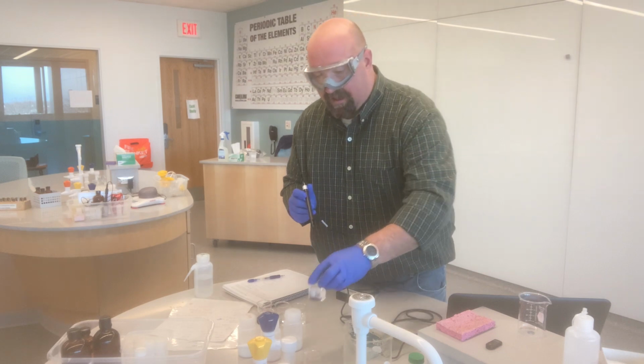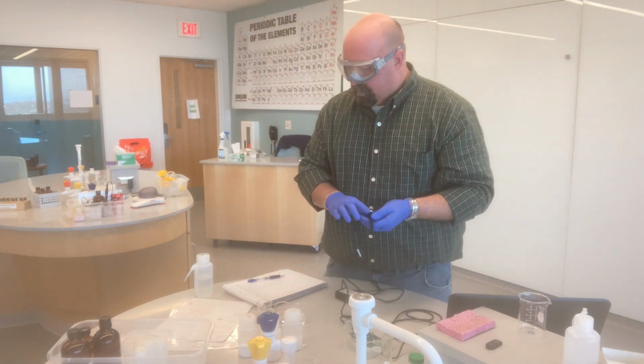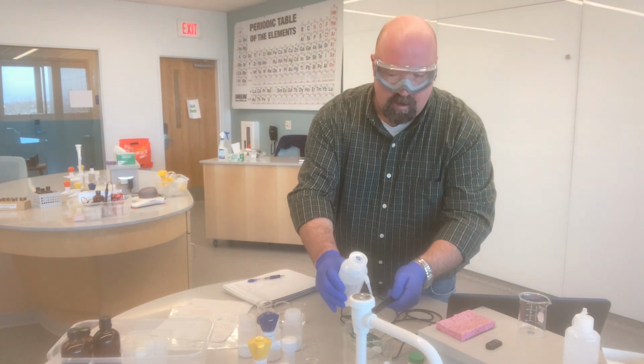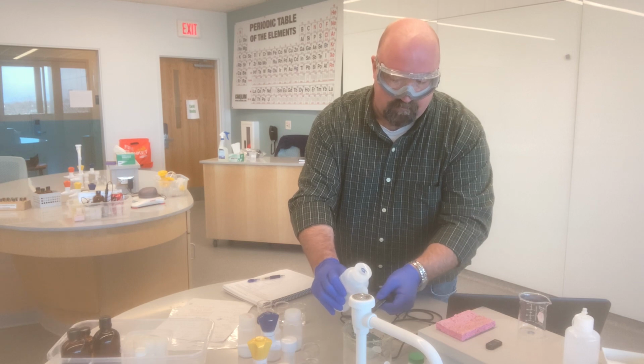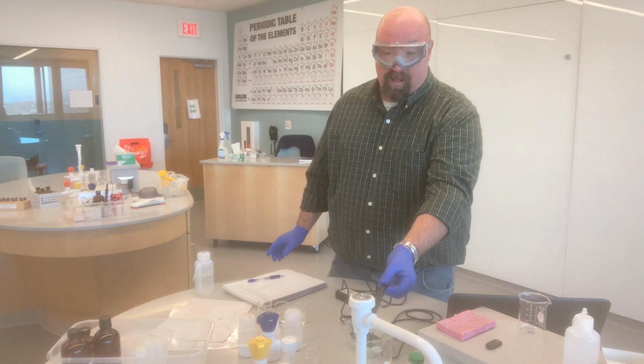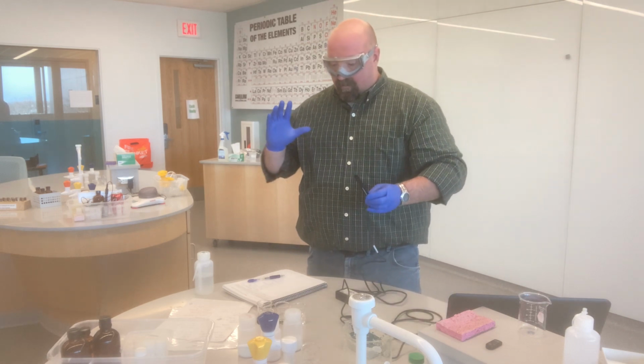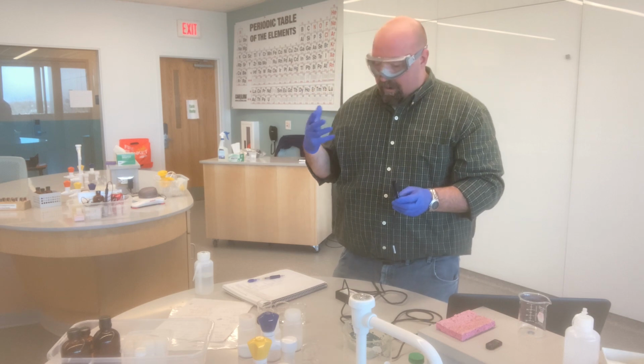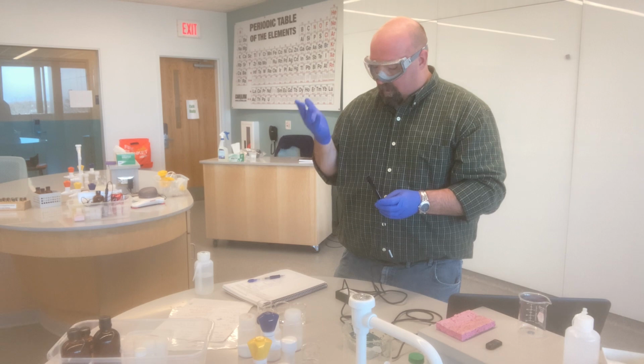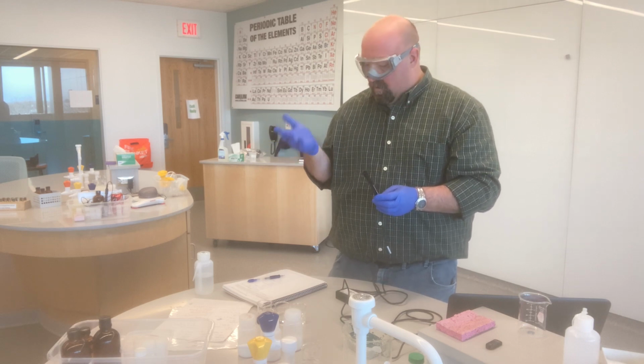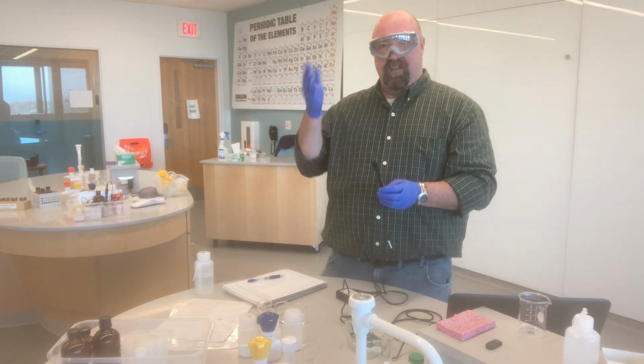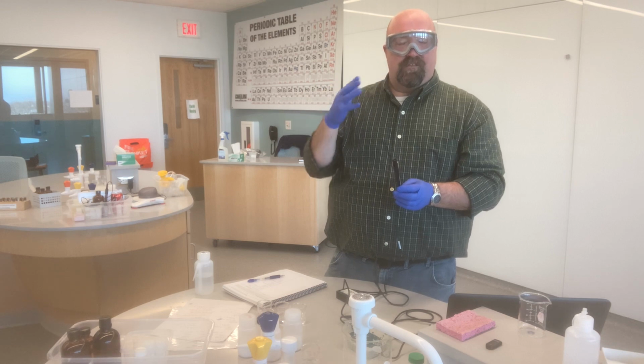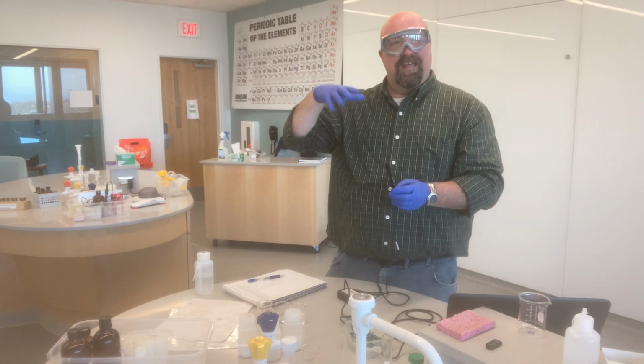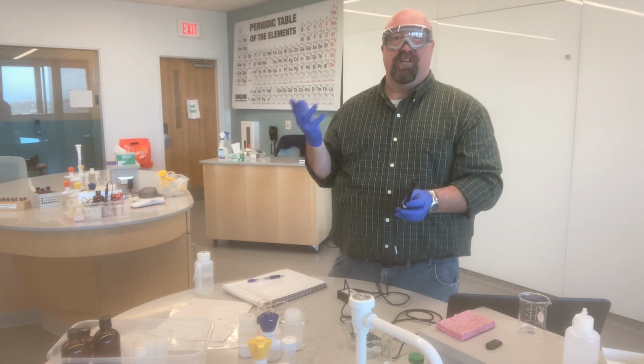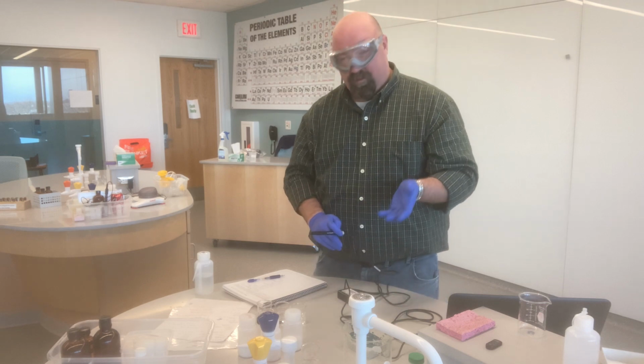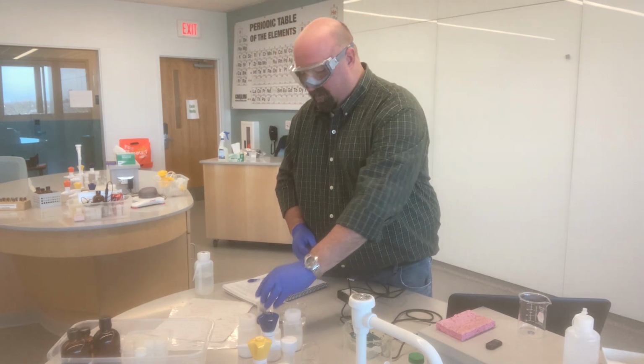Now you may note, just as a side note, that all the measurements I'm reading, I'm only reading off to the tens spot, except for my very first one. Conductivity probes are fairly sensitive, and so this is something, unfortunately, that you can't really see. I have my camera set up well right now, so I don't want to move it. But conductivity measurements jump around quite a bit. On that last one, I was watching it fluctuate between 2587 or so and about 2600. So it kept bouncing around in that range. Once I saw that it was bouncing around just in that range and not going beyond it, I did an internal estimate and said, well, it's basically bouncing all around 2590. And so I made the judgment that that's what the measurement was. That's why these are all only going to the tens spot.